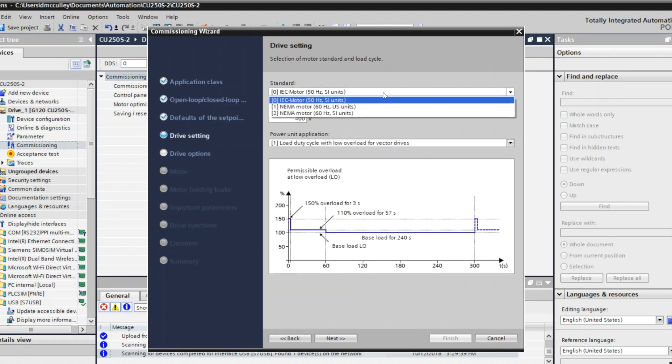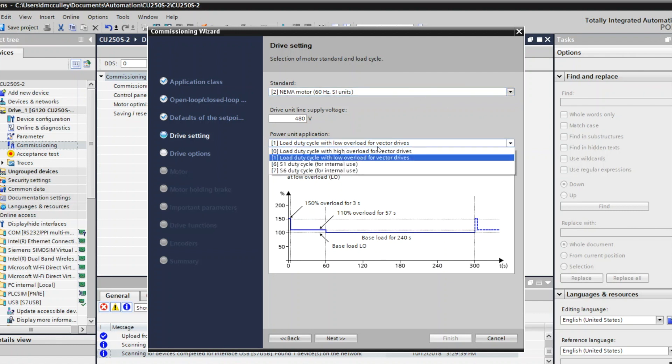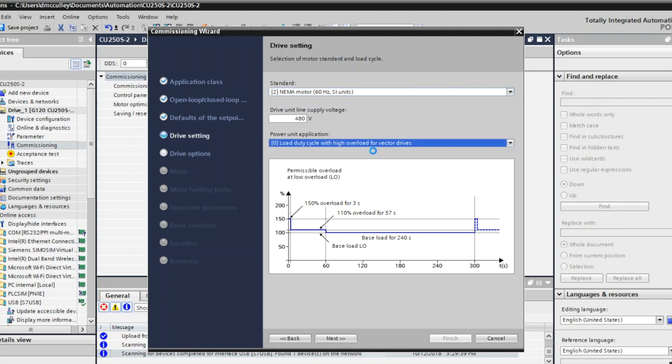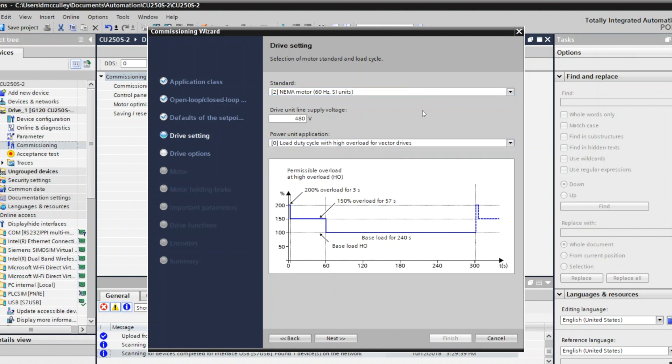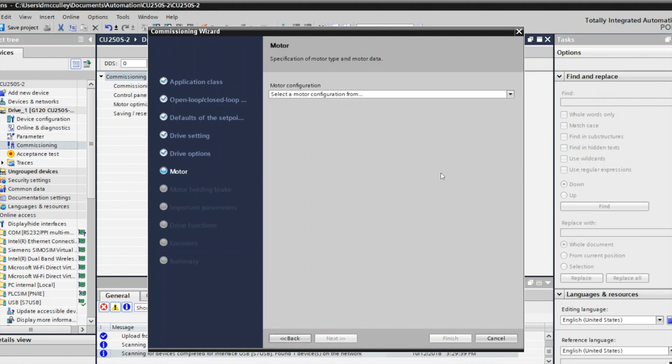I have a NEMA 60 Hertz motor with SI units on it, and my voltage for the input to the drive is 480 volts. I'm going to choose high overload for vector drives because I'm going to assume mine's a conveyor. Low overload would be for fans and pumps. I don't have a brake resistor or filter.